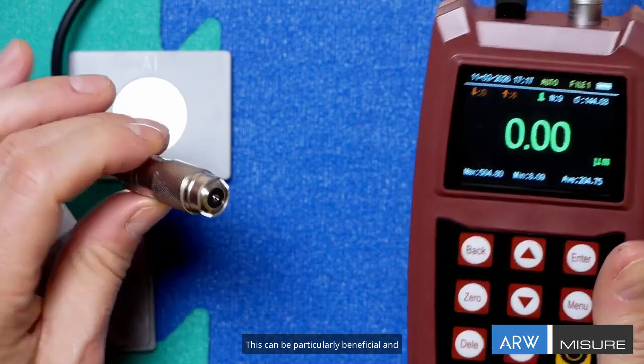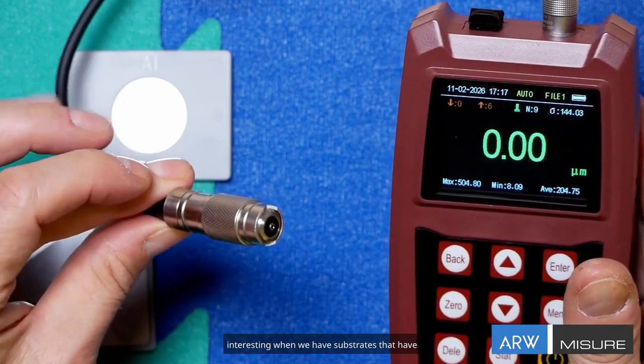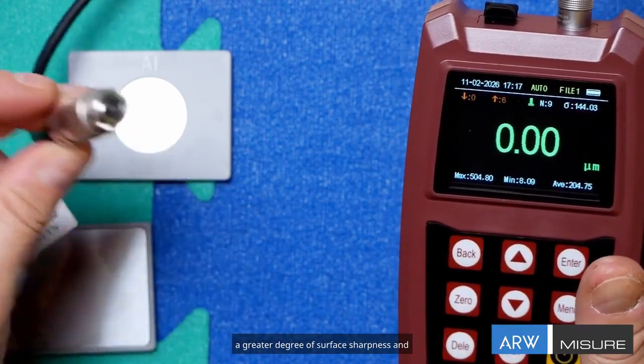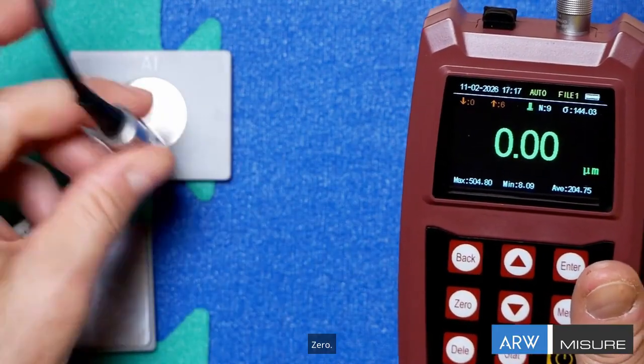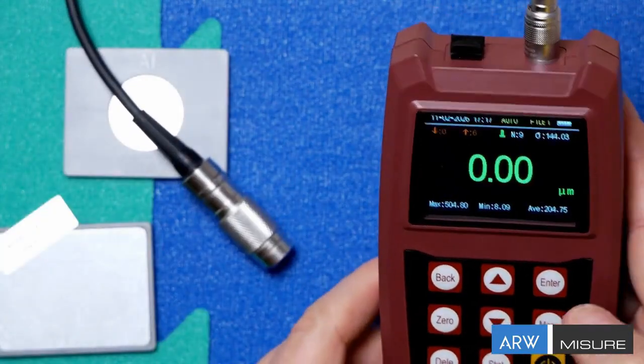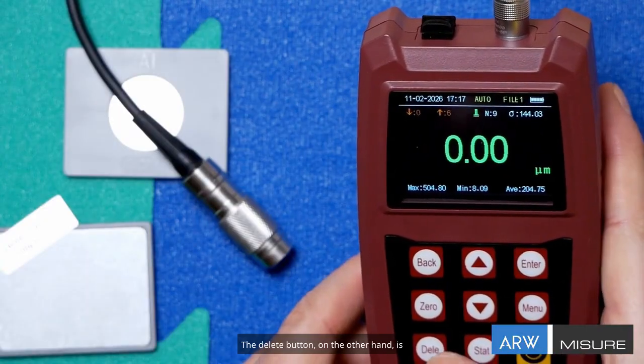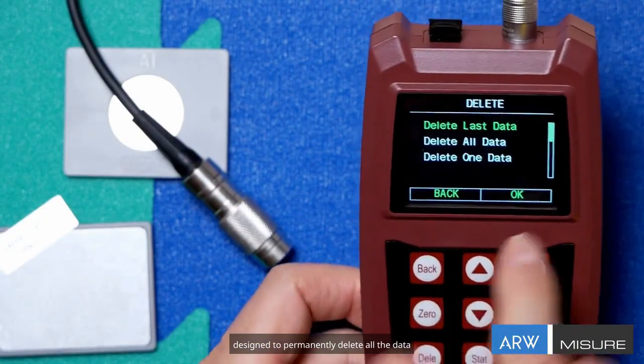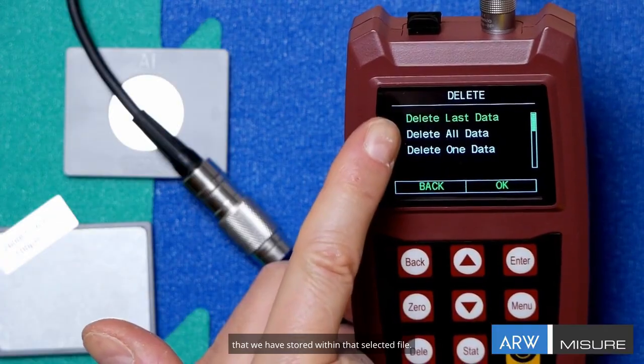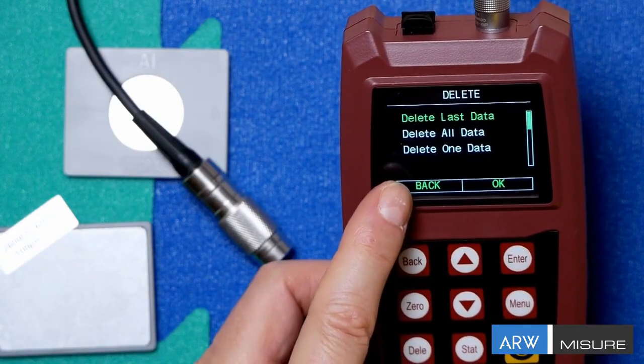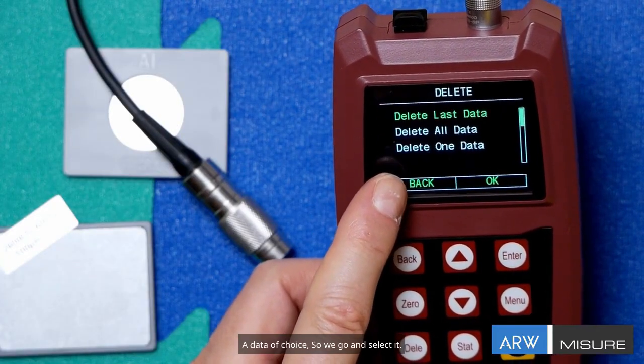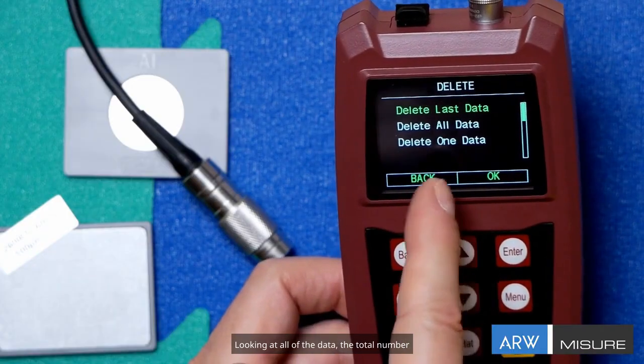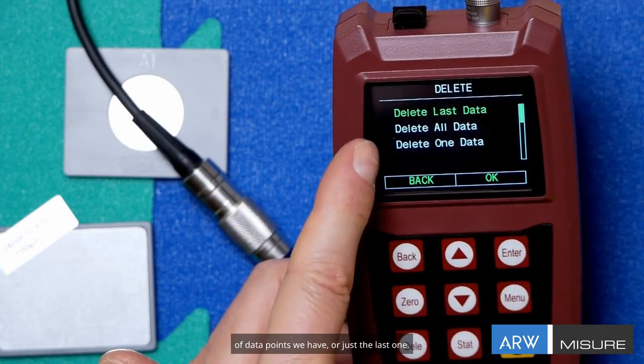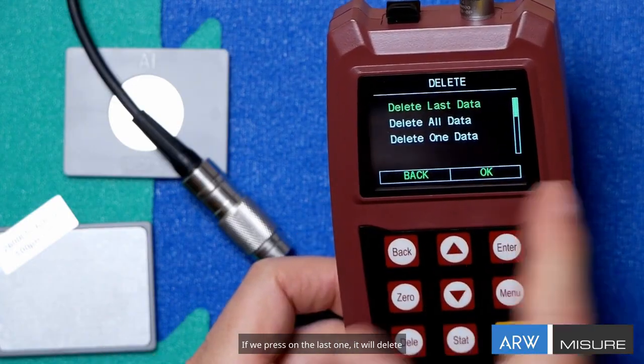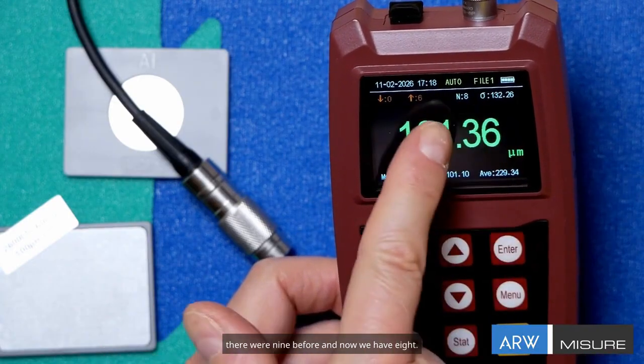This can be particularly beneficial when we have substrates with a greater degree of surface roughness and perhaps we need to take many more points. Zero. The delete button, on the other hand, is designed to permanently delete the data we have stored within the selected file. We go and select it, looking at all of the data, the total number of data points, or just the last one. If we press on the last one, it will delete that last entry. There were 9 before, and now we have 8.